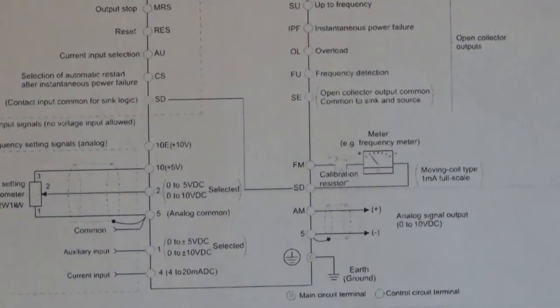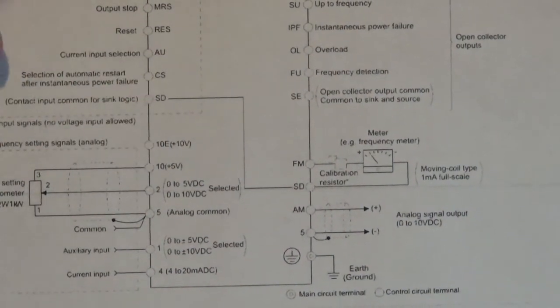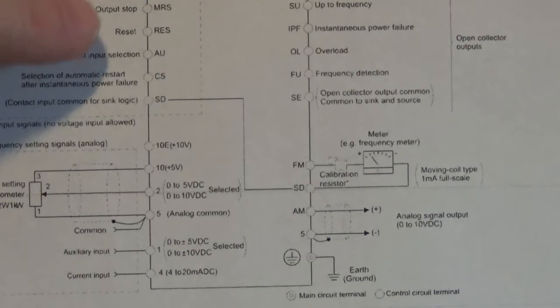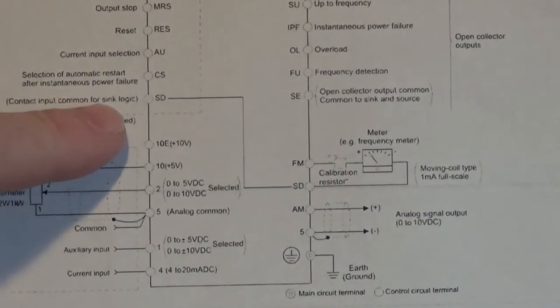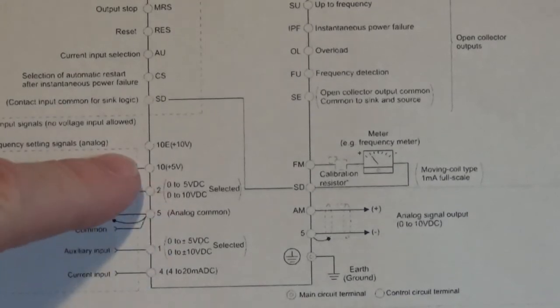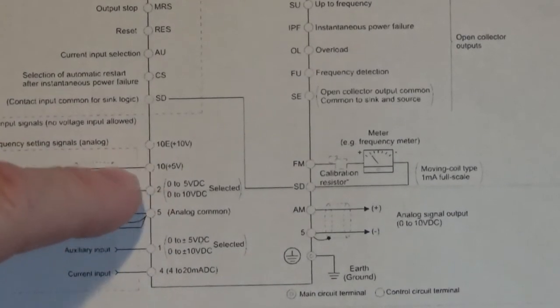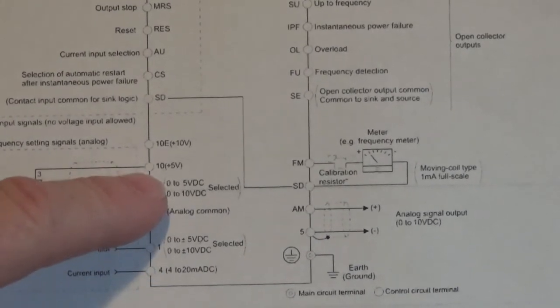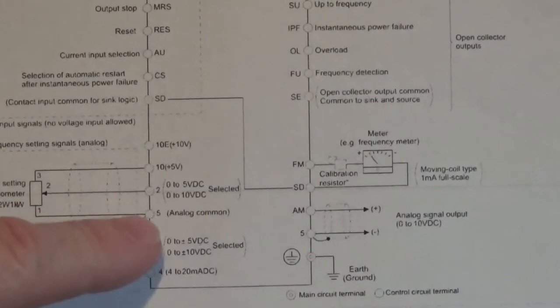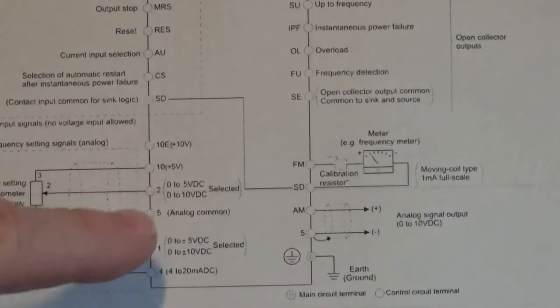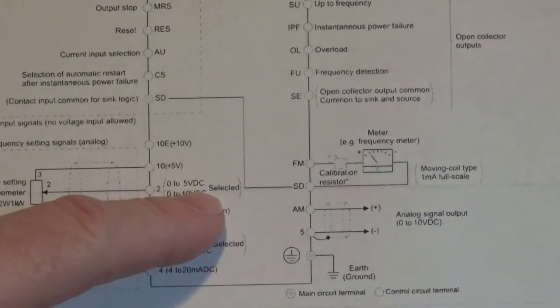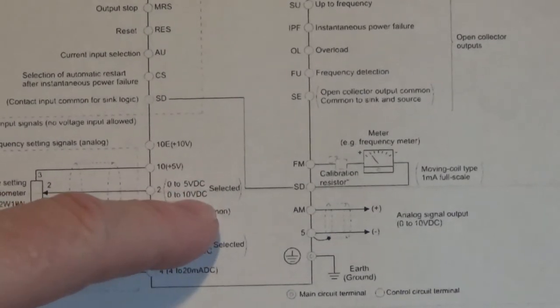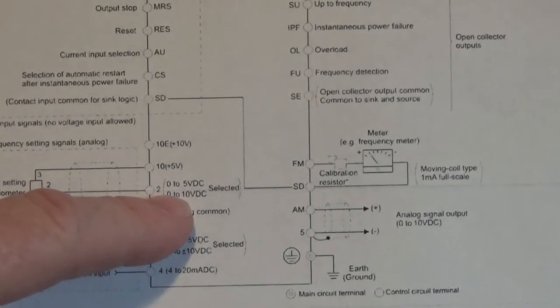Let's move down there and we'll look at that SD and the potentiometer input. Now right here is the SD terminal that we connected STF to to make the drive run forward. It says contact input common for sink logic. Now here's terminals 10, 2, and 5. 10 is plus 5 volts, 2 is your 0 to 5 volt DC or 0 to 10 volt DC speed reference input.